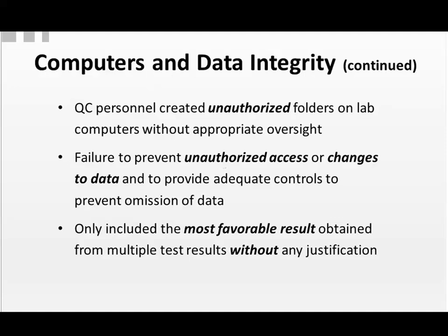Here, QC personnel created unauthorized folders on lab computers without the appropriate oversight. So they had folders on their systems that had data and files in them, but there was no oversight to that, no record of why that was being done or what that meant. Again, failure to prevent unauthorized access, someone accessing functionality, changing data that they should never be able to do, or providing adequate controls to prevent the omission of data.